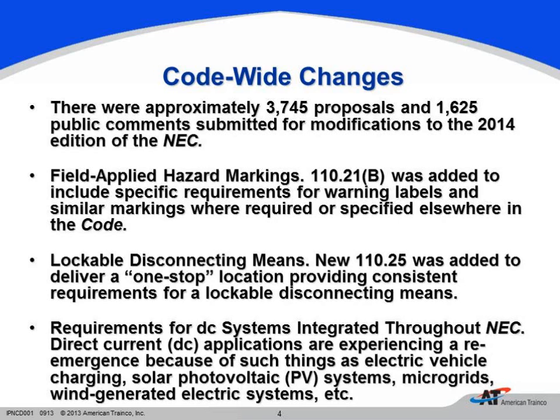So electronically, they are giving us a chance to get a power source coming in, and then going out, we can change that to whatever we need. Another new definition that they put in photovoltaic systems is a combiner. So it's a DC combiner, and it is used to allow two or more DC inputs, and then it provides us with one DC output. So that's going to be very important to the photovoltaic industry.